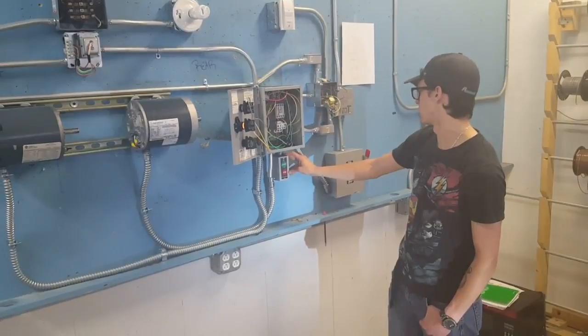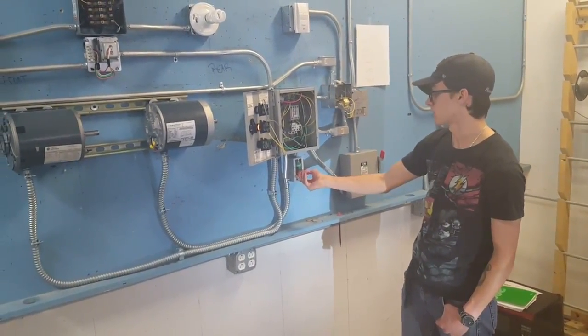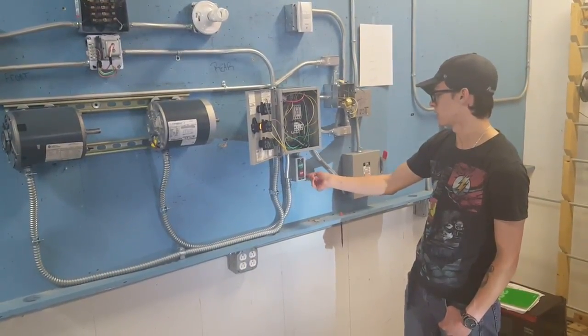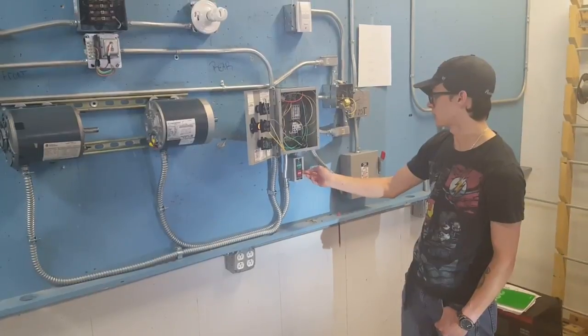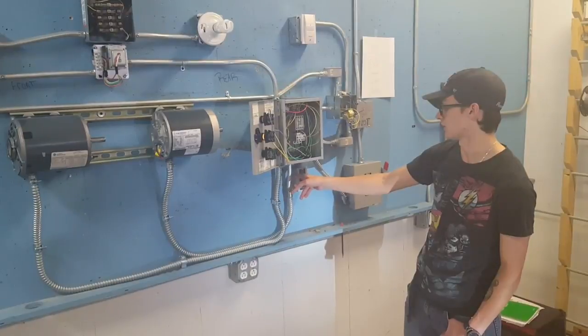We wire this so the power is coming off one of the three phases going directly into the stop button, which is a normally closed contact. That stop button is coming out into the input of the start button, which is a normally open contact.